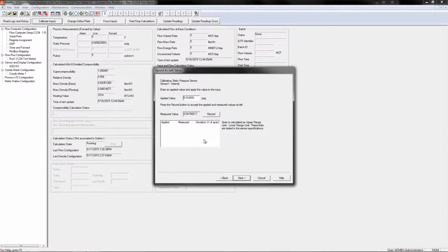Okay, now for the as founds, for the sake of this video, I will pretend we do a six point as found: 0, 50% of the span, 100% of the span, ascending, and then descending we go from 100, 80, 20, and then back to 0. So we span this to 500, so at this point I would do 250. 500, and of course then we would go down, leaving this offset there from the spreadsheet. I like everything I see, so I hit next.